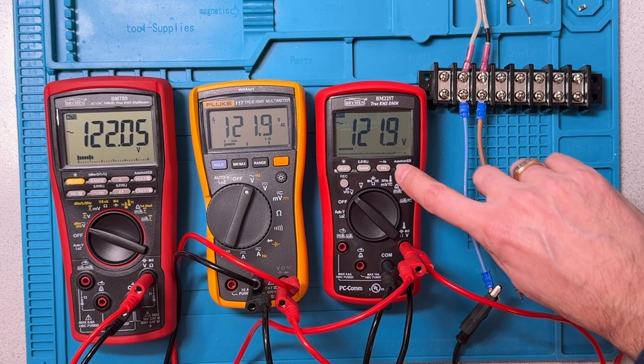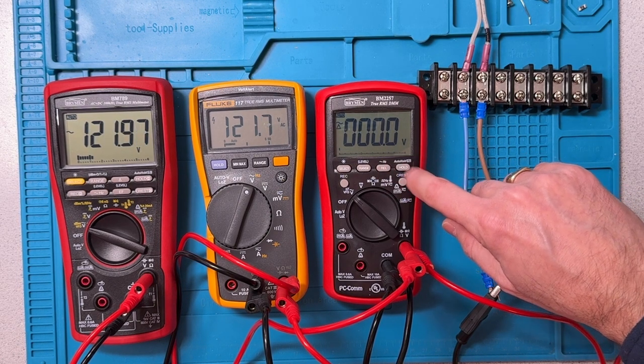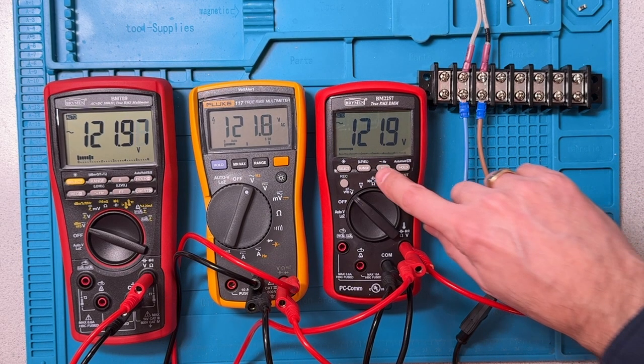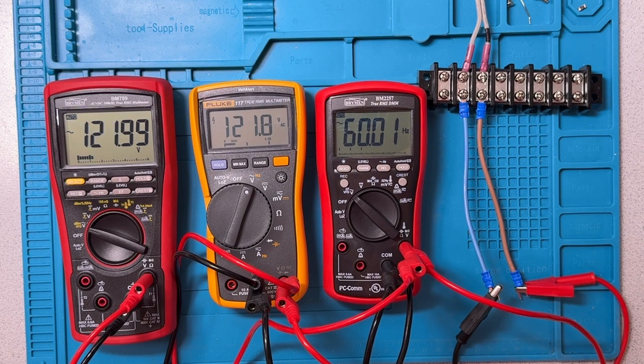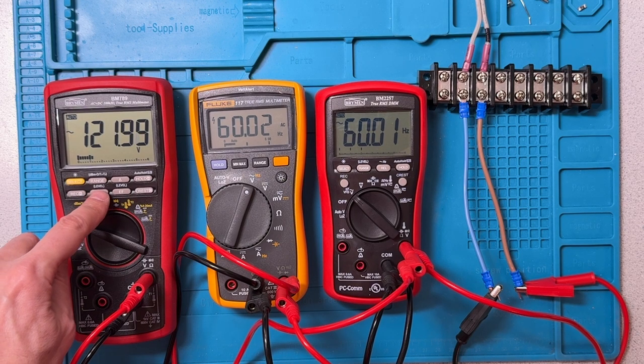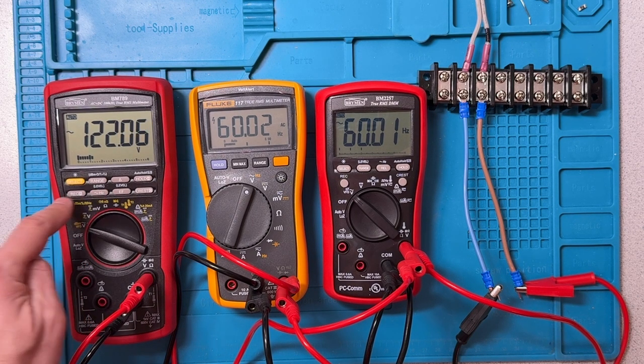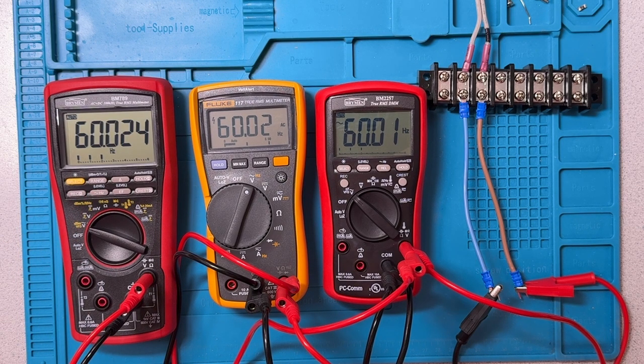Now we can get the frequency for all of them here. So if we hold that down, 60 hertz there on the Fluke, hold that down, and on the 789. So we can see that the frequency, they're all showing pretty close to the same frequency, the 789 and the Fluke kind of showing 60.02 or 01 depending upon the rounding, and the 2257 generally showing closer to 60 hertz dead on.